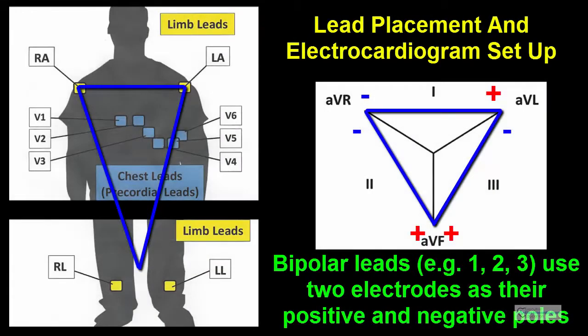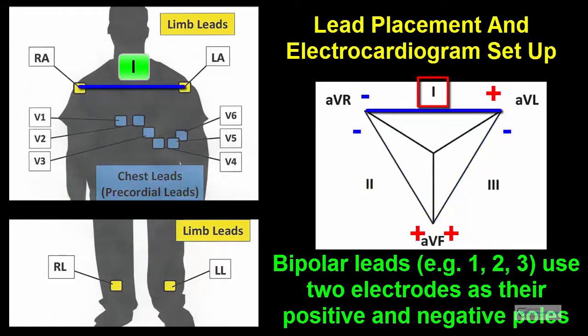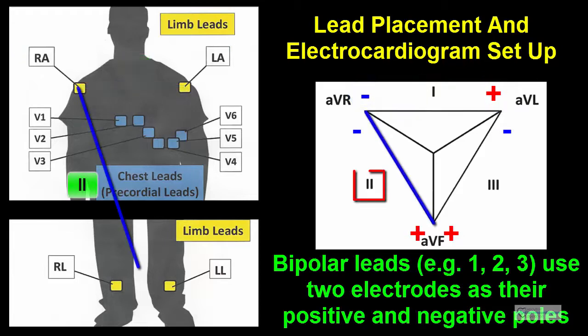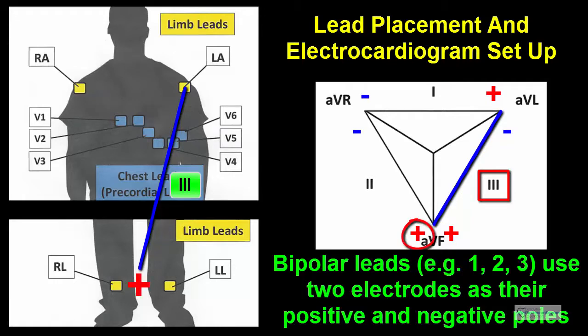Bipolar leads, such as leads 1, 2, and 3, use two electrodes as their positive and negative poles. For lead 1, the positive pole is the left arm electrode, while the negative pole is the right arm electrode. For lead 2, the positive pole is a leg electrode, while the negative pole is the right arm electrode. For lead 3, the positive pole is also a leg electrode, and the negative pole is the left arm electrode.